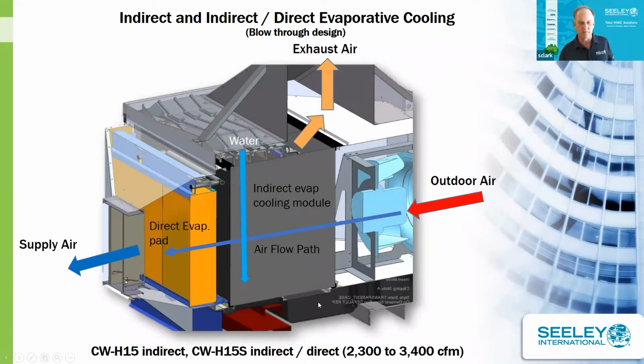wet sheets. That water comes into a sump where we have a pump that continuously recirculates this water. We also have a conductivity probe in the sump that will automatically blow down the sump, the water reservoir, to keep the minerals within a certain specification. That's how we get rid of our minerals. We also have a chlorinator in here. So we're generating free chlorine in this sump electronically, to keep any bacteria at bay.